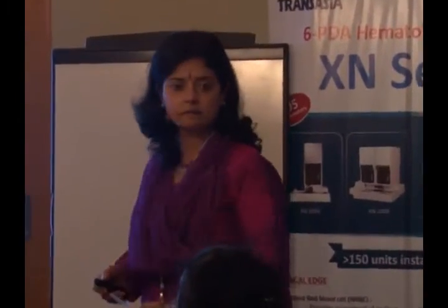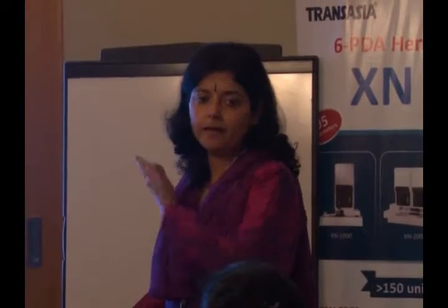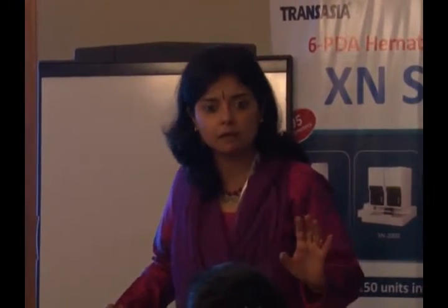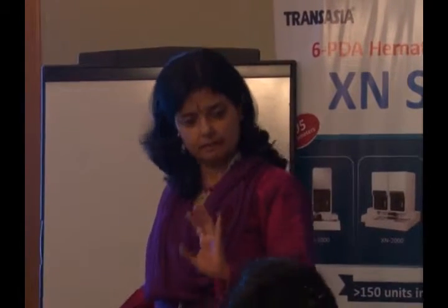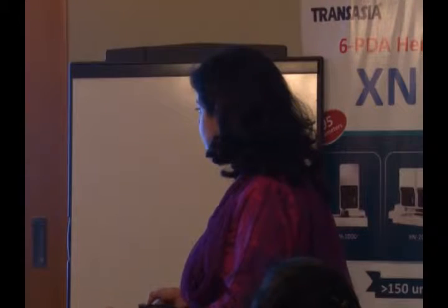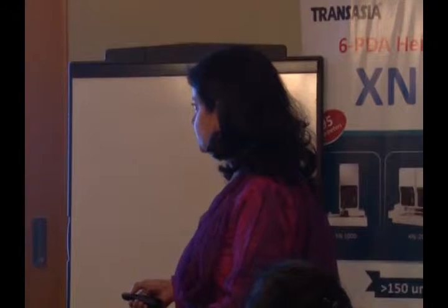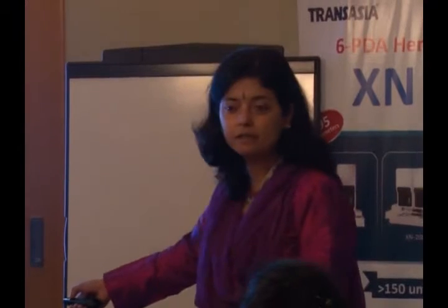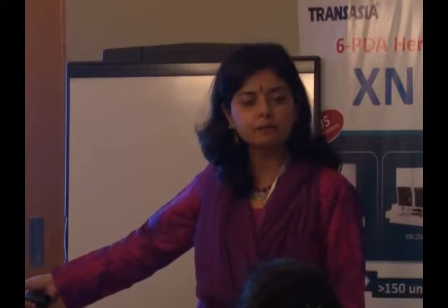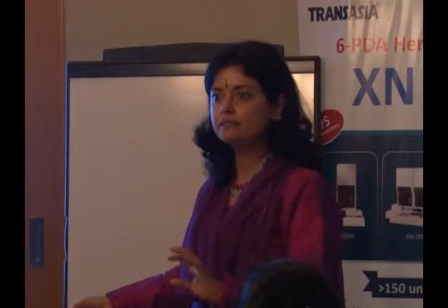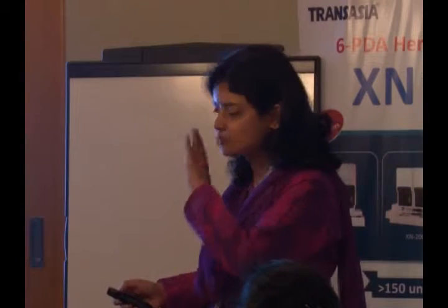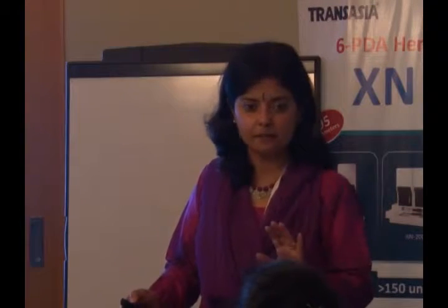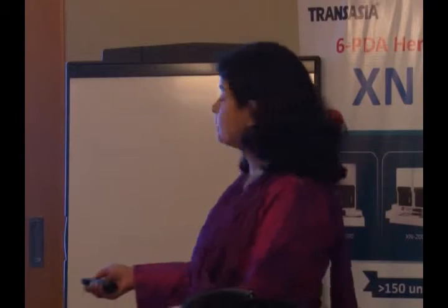So is impedance counting large platelets as RBCs? No. We don't know when. They may not count at all. Just leaving it. Now you see, right now it's fine, you are getting an MPV, okay, I will show you, no MPV here, no MPV. So what do you do? You can't use MPV. To me, MPV is, I'm sorry, within four walls, I said it in Chicago, the most redundant of all platelet parameters in low platelets. Okay? Don't quote me on this.